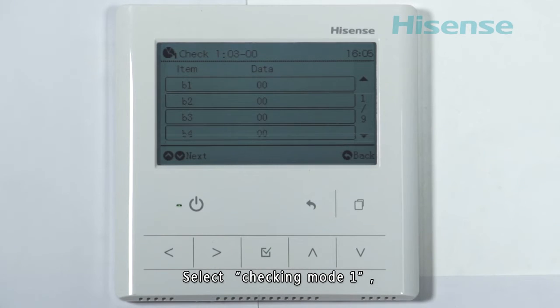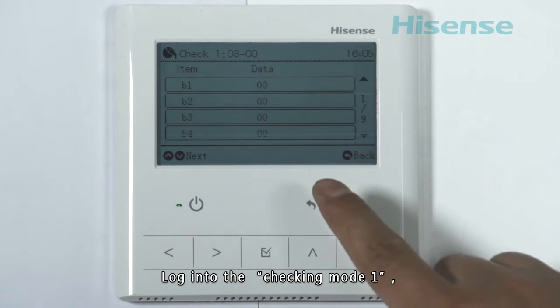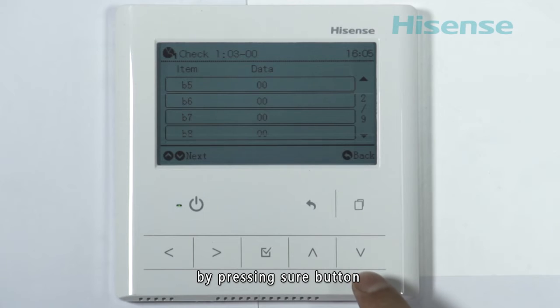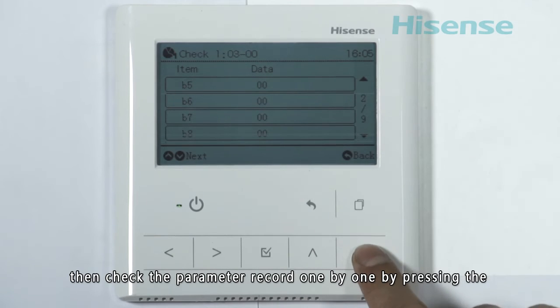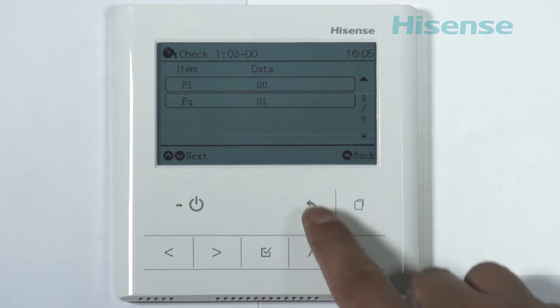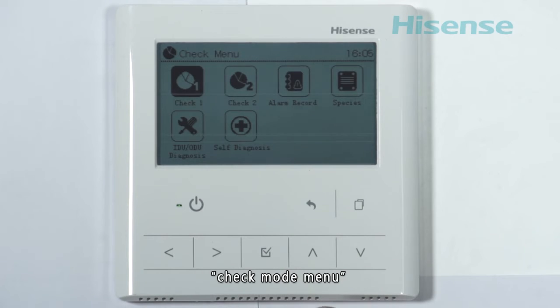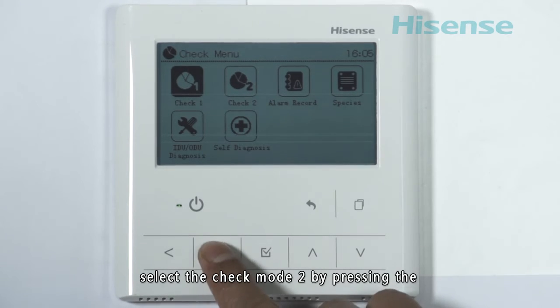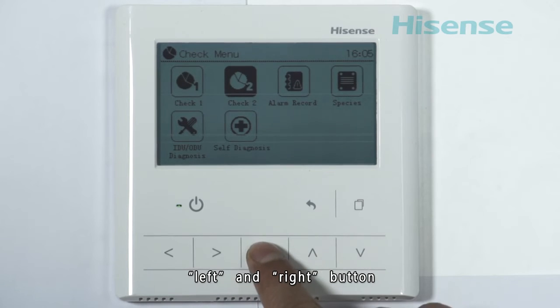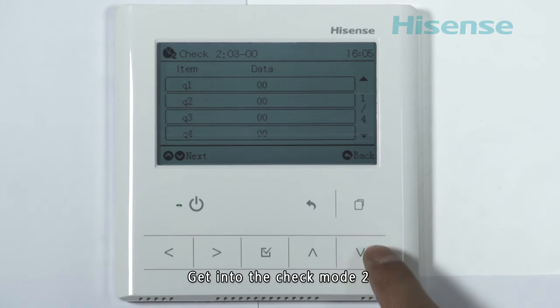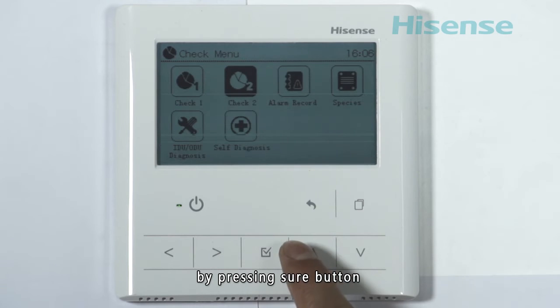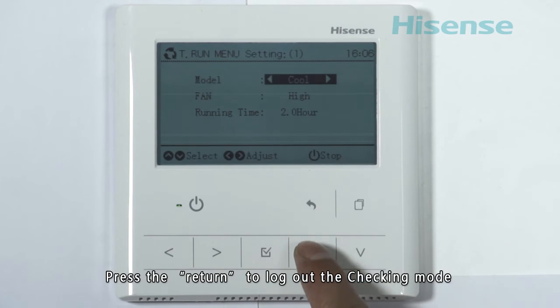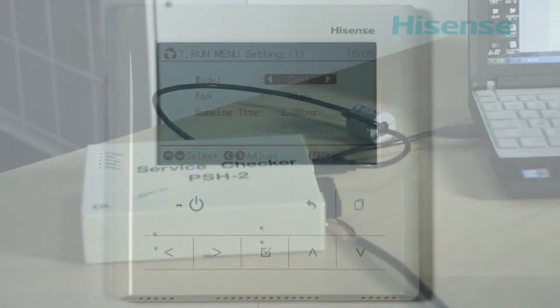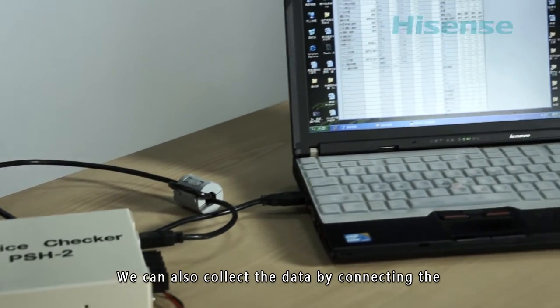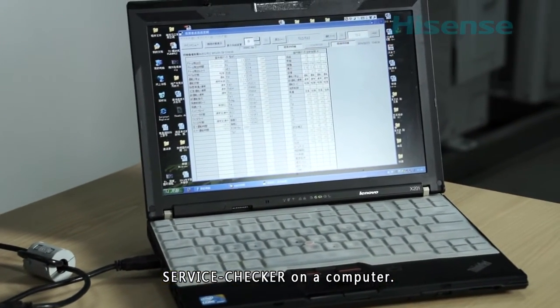Select Checking Mode 1. Log into Checking Mode 1 by pressing the Sure button. Then check the parameter records one by one by pressing the Up and Down buttons. Press the Return button to go back to the Check Mode menu. Select Check Mode 2 by pressing the left and right buttons. Get into Check Mode 2 by pressing the Sure button, and press Return to log out of the checking mode. We can also collect the data by connecting the service checker on a computer.